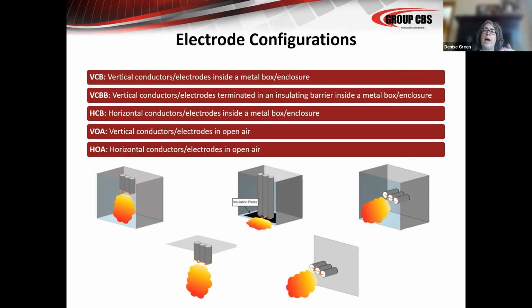So they also added a component where there's an insulating barrier to the mix. So insulating barriers versus open transition, in equipment, where an arc flash incident can get contained better in a situation where there's insulating barriers versus not.